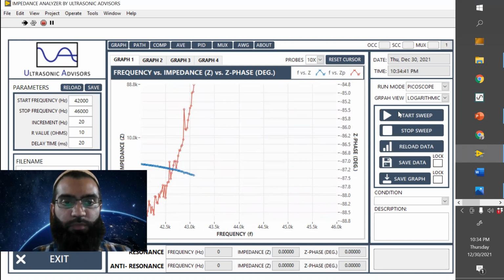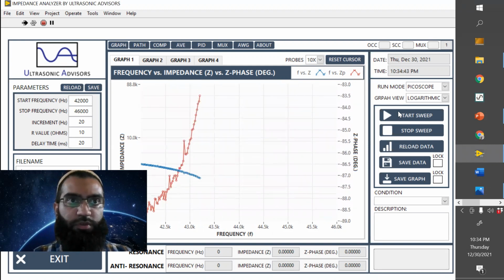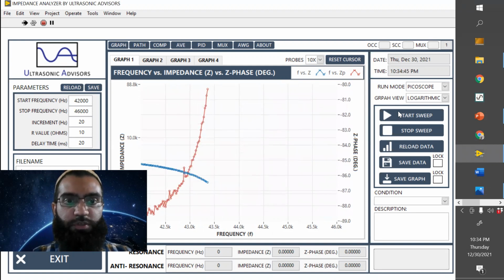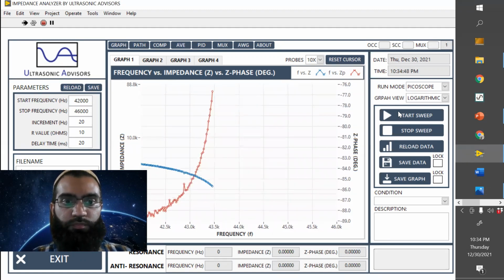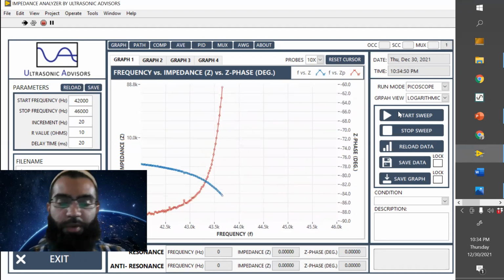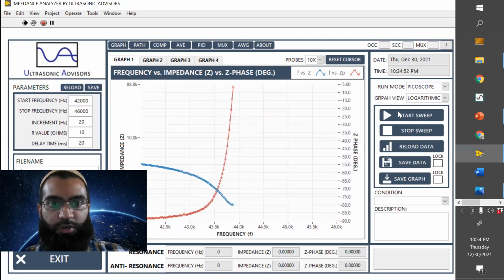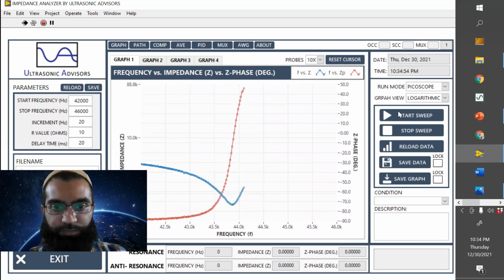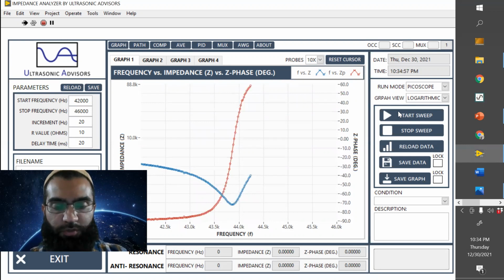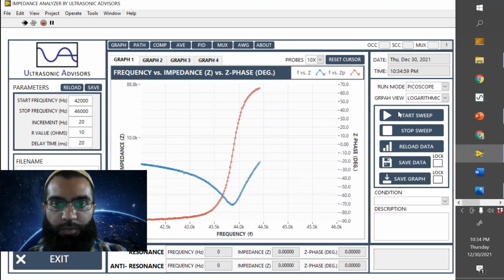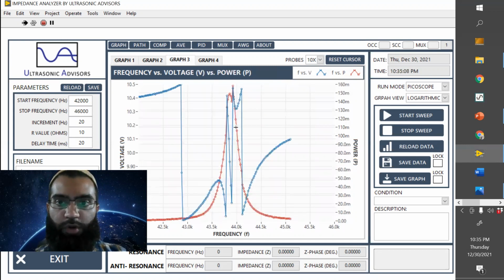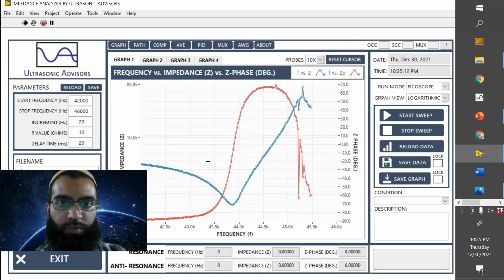This just takes a little bit because it's doing its amplitude adjustment. There's also a delay time I put in here in case anything needs to settle out. It looks fairly symmetrical, the resonance point, although we are using constant voltage, so it's not really stressing it too much. And if you look at the power graph, we're now at 150 milliwatts for 10 volts.